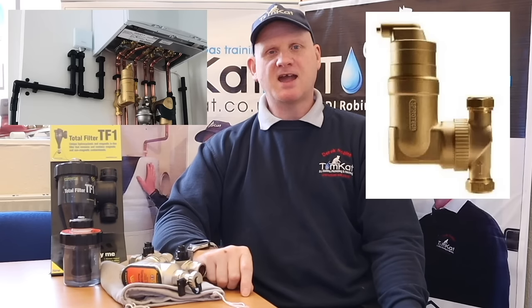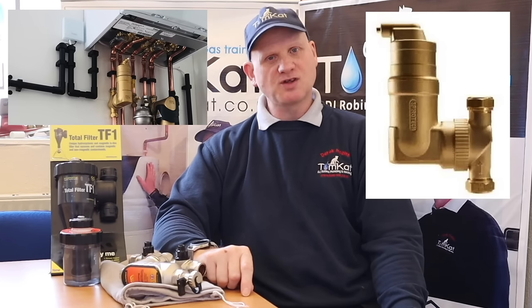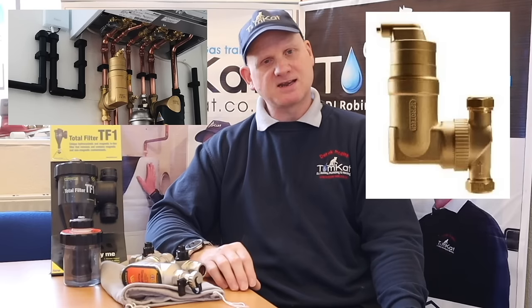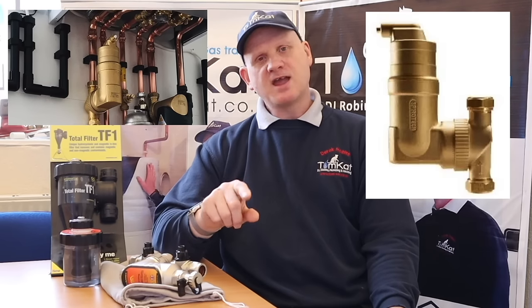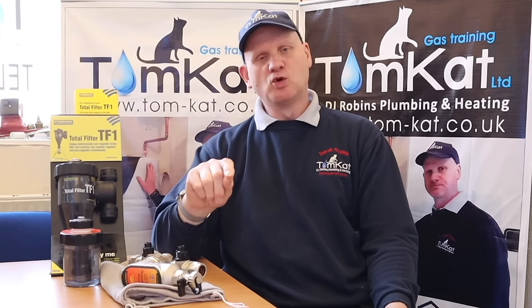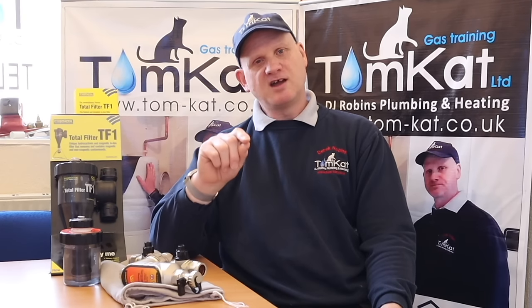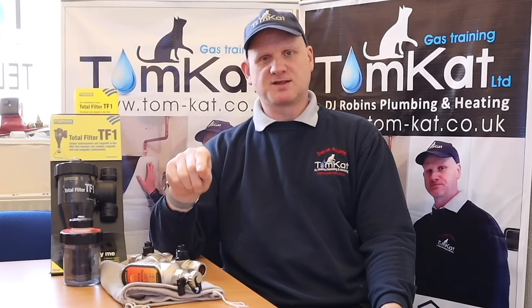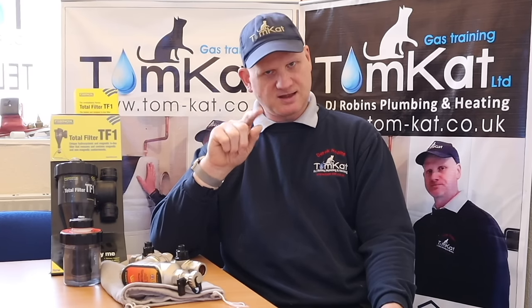So we are treating the problem, we are not creating a cure. Fitting a deaerator into the system is just as important as fitting one of these magnetic filters. This deaerator will remove the air in the system, which will also stop corrosion. And this technically would remove the need for dosing inhibitor. But we must dose inhibitor to comply with the current regulations. Another way of prolonging the life of this boiler and this system is balancing radiators. So let's have a look at that.